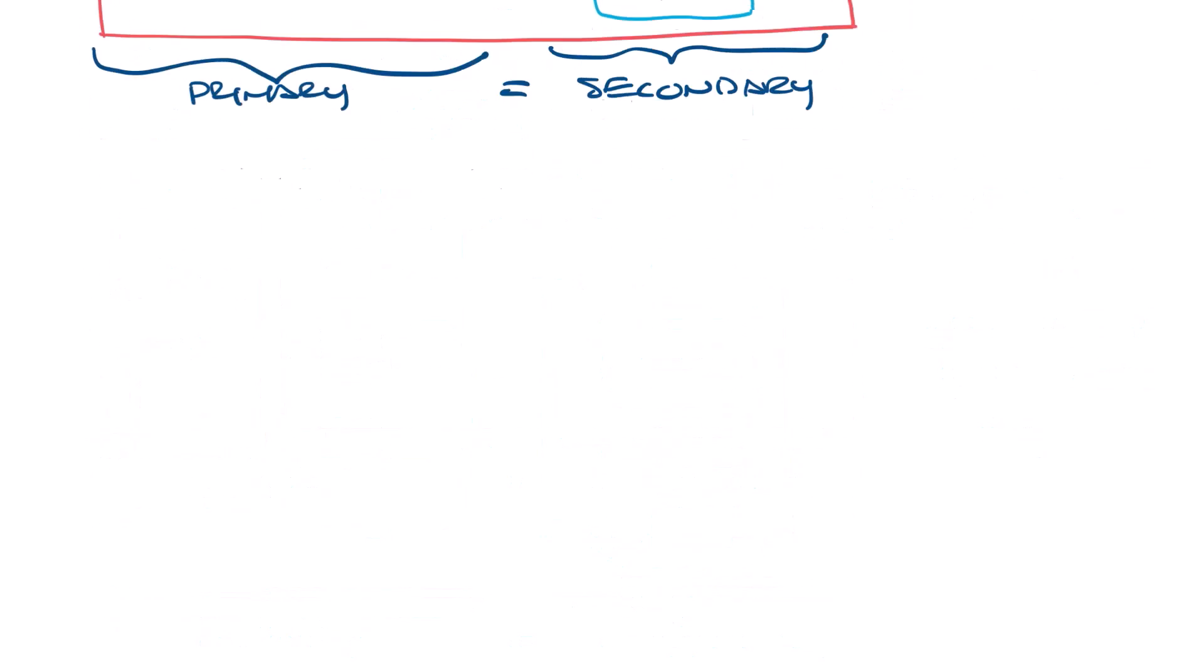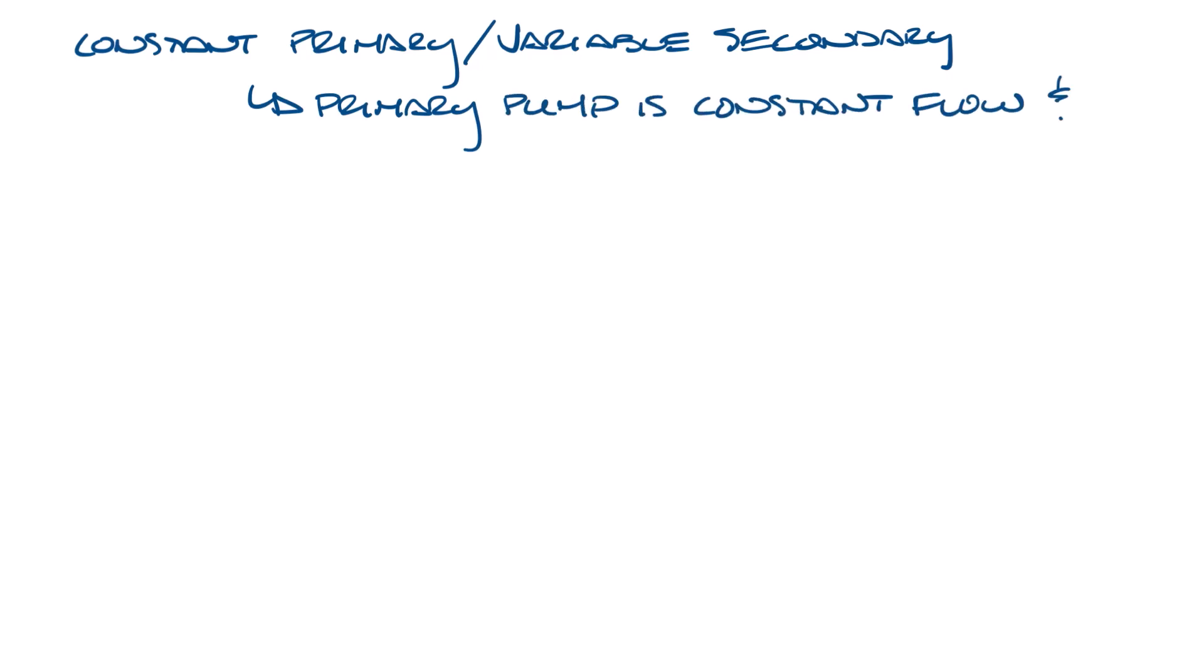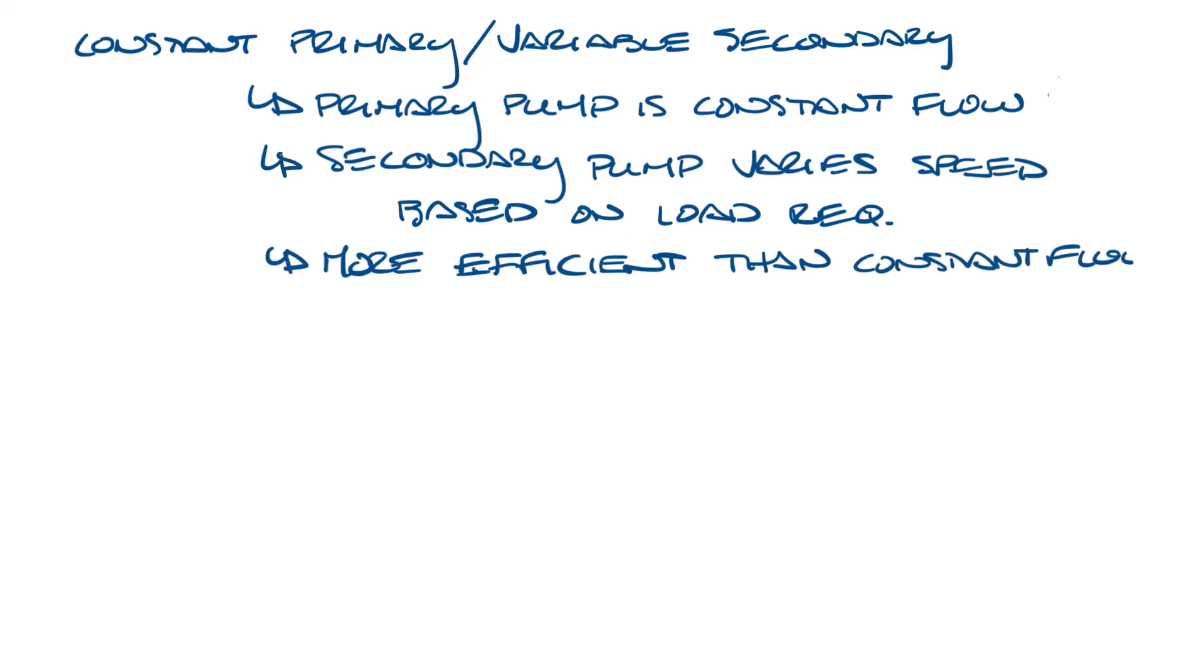So let's move this over and look at the constant primary variable secondary circulation system. This is often called primary secondary system. The primary pump is running at constant speed, but the secondary pumps are varying their speed based on load requirements. With the secondary pump being variable, the system is more efficient than constant flow systems, since the secondary pump only uses required energy to meet the system demand.